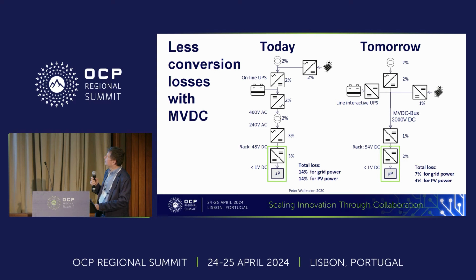So here, this is what we have today. And we see that for the grid power, when we sum up all the losses, it's summing up to 14% losses. This is also the case for the PV energy, which might be used. So if we use PV energy, we have to inject this on AC side and with a converter. So the concept looks very different when we use a medium voltage DC grid for powering the data center.